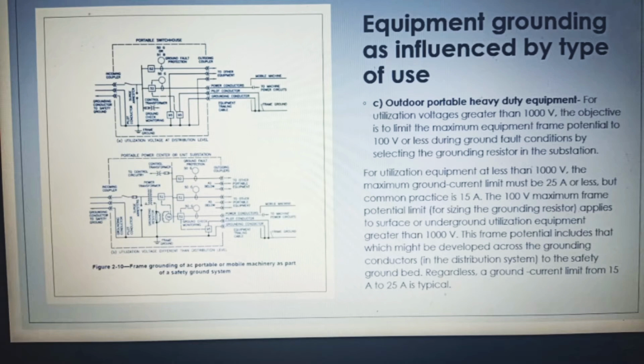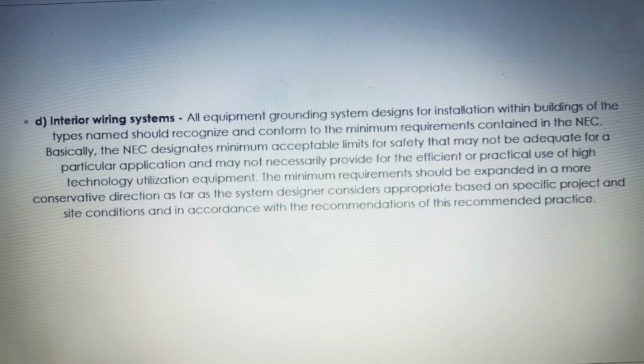The ground current limit varies as to application and system voltage. For utilization equipment less than 1000 volt, maximum ground current limit must be 25 ampere or less, but common practice is 15 ampere. The 100 volt maximum frame potential limit applies to surface or underground utilization equipment greater than 1000 volt. This frame potential includes that which might be developed across the grounding conductor to the safety ground. Regardless, a ground current limit from 15 ampere to 25 ampere is typical.